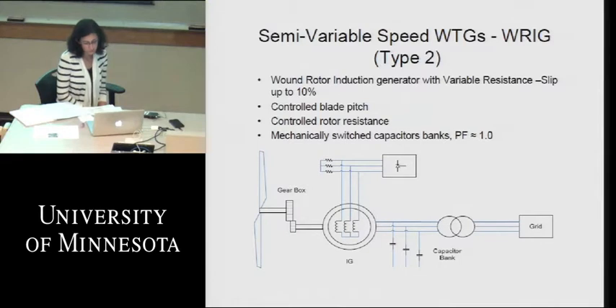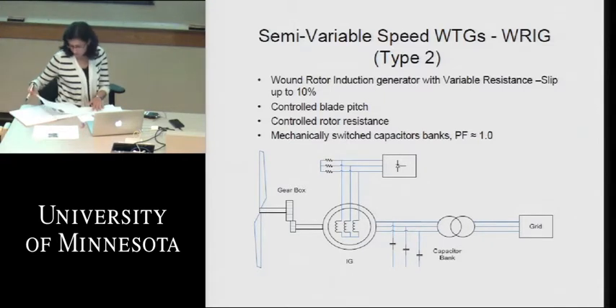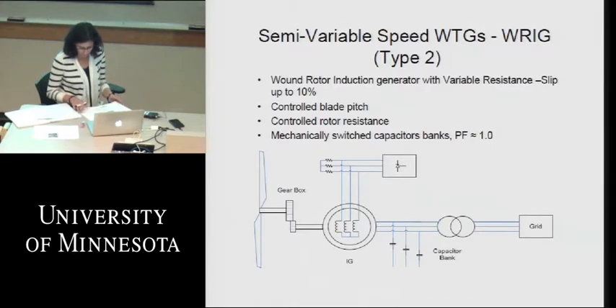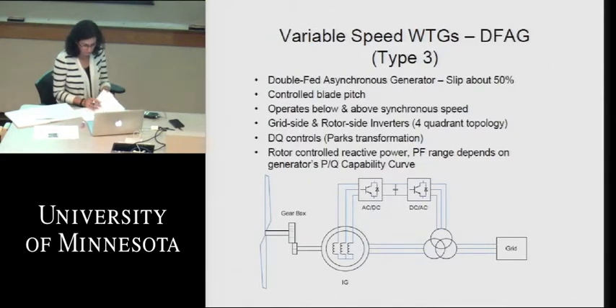And that was fine for how wind turbine projects were run until about 10 years ago. But because of the success of wind, we've had to come up with new control strategies. As wind turbines got larger and the projects got larger, and there are more projects going onto the grid system, we are having a much larger impact today than we did 10, 15 years ago on the overall power delivery that the grid provides to all its loads. So we've had to change our control schemes, evolving from the Type 1 to the Type 2. And now, next slide, we've evolved to the Type 3, which is the state-of-the-art as of today.